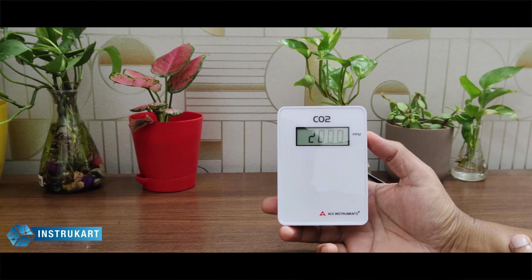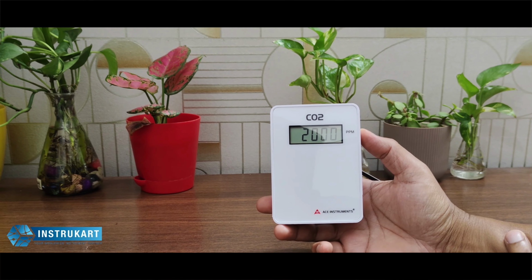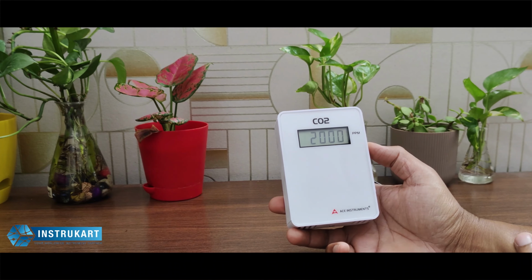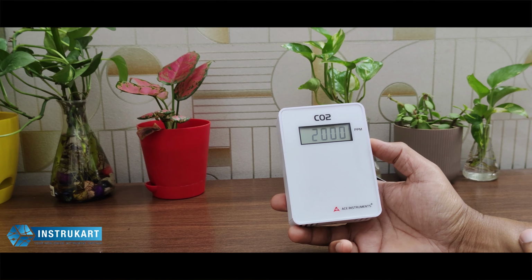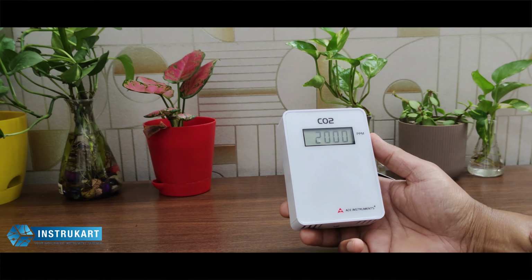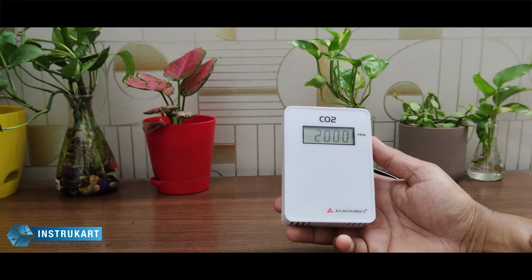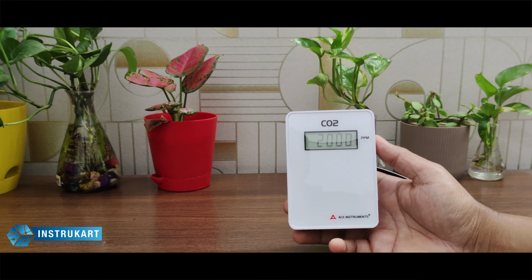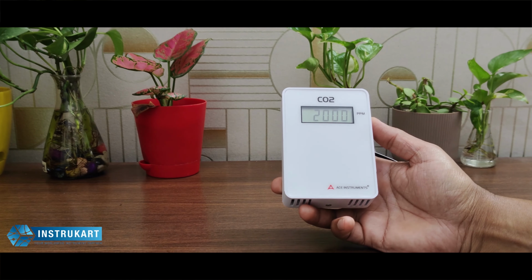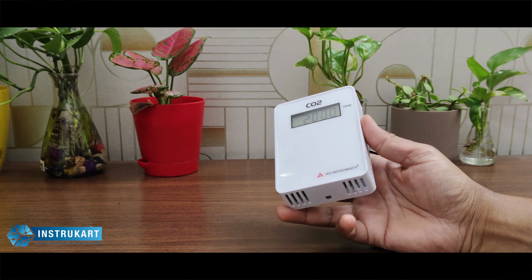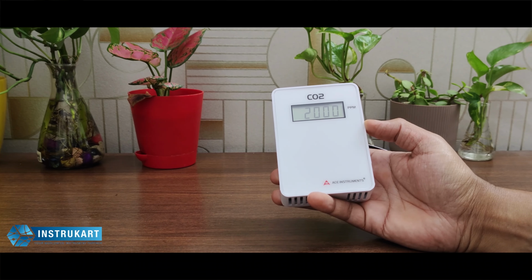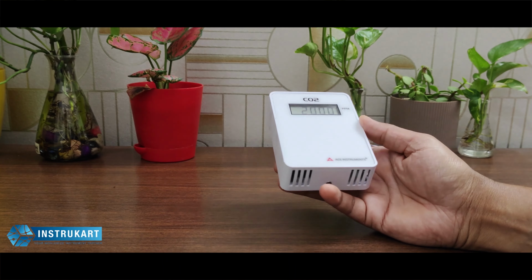Also, it has got a relay option wherein you can control your fan, motor, exhaust or anything, or do a cutoff with this relay NO/NC. This has also got a non-display option, which means that if you just need a transmission, you can use the non-display CO2 option. Apart from this wall mounting, we also got the duct mounting CO2 transmitter available, because at the duct also we require to understand in the HVAC system how much CO2 is present.